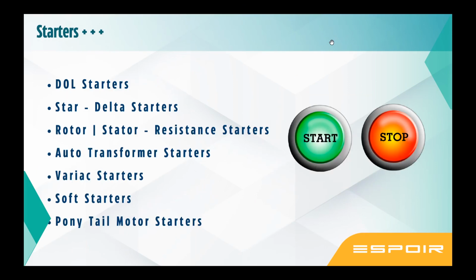Now, with motors, what we generally have are starters to start or stop from the beginning. There are different types of starters: DOL starter, star delta starter, rotor or stator resistance starter for slip ring induction motors where high starting torques are required. In certain applications in the beginning of the era, there used to be auto transformer starters. Then came the soft starter. And there are certain starters like pony motor starters, which is a very big subject to talk about. Maybe we can cover it in the series too. Soft starters have been there for a long time, but still it has not come to a point where it should be used.